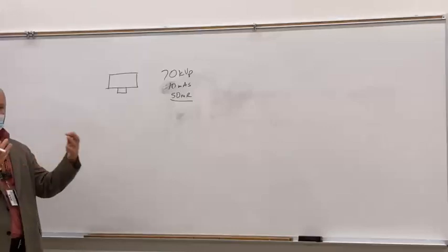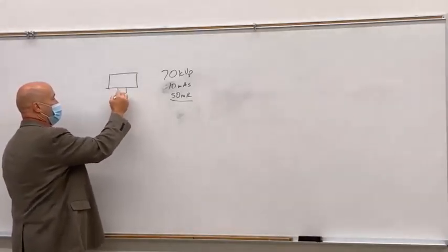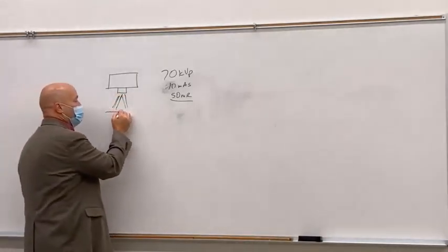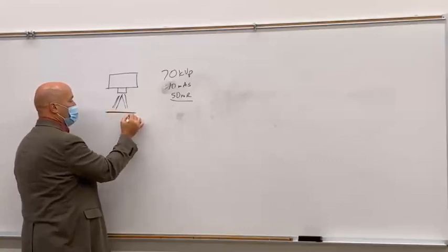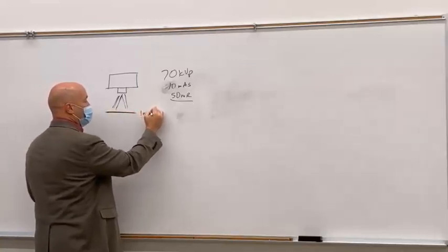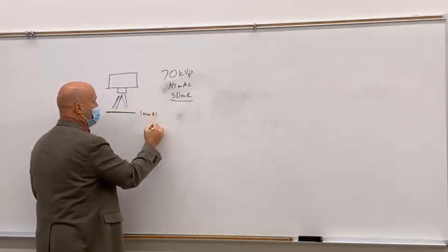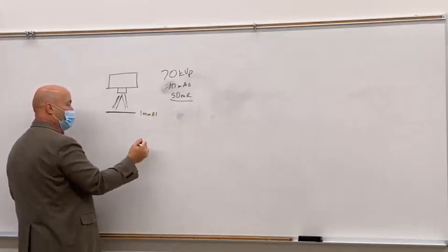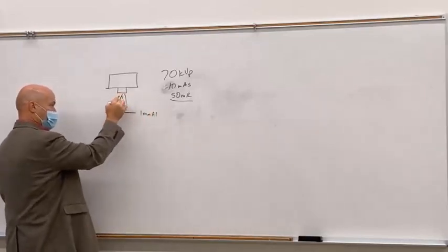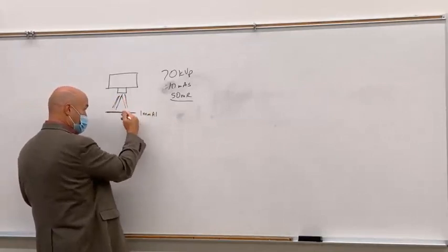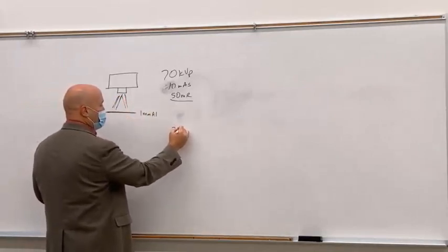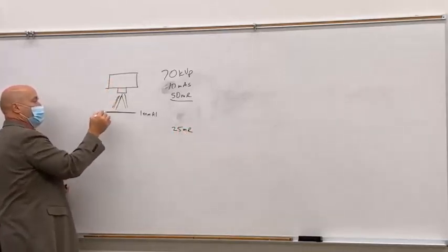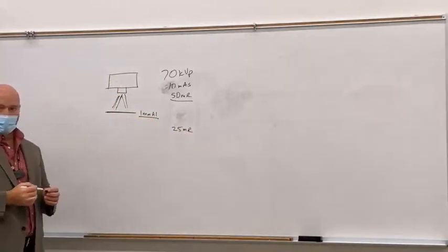It's not hitting anything. This is the exposure just below the X-ray tube, right? So that's the amount of radiation coming out of the X-ray tube. So if you were to take an absorber, say this is 1 millimeter of aluminum, and with that 1 millimeter of aluminum, he measured the exposure up here, and then he measures it below the aluminum, and if it comes out to 25 MR, then that X-ray tube's half value layer is 1 millimeter of aluminum.